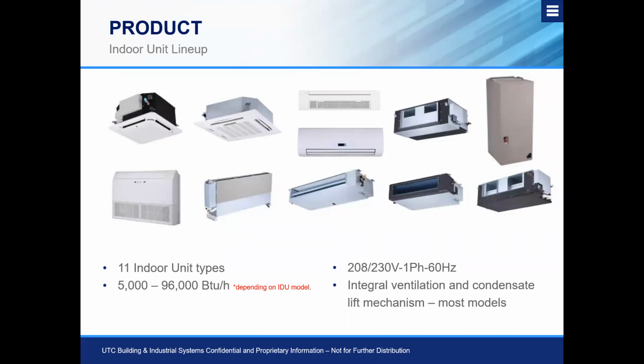And we have our ducted options. Working from left to right, we have our low static unit, which is going to offer up to 0.2 inches of static pressure. To the right of that is our mid static unit, which is going to get up to about ½ inch of static. And then finally on the right is our high static unit, which goes all the way up to 1.1 inches of static. So all in all, we have 11 different indoor unit types.